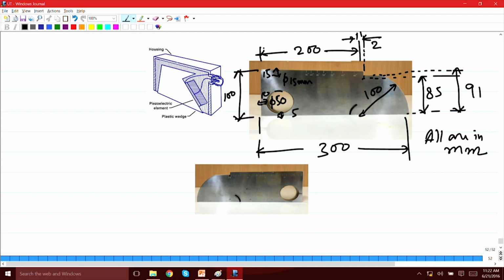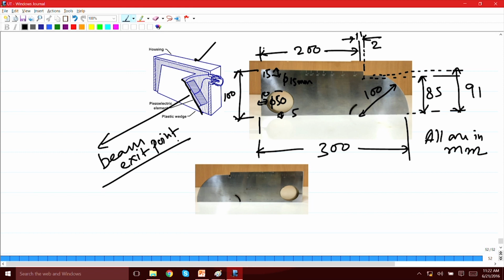This is an angle probe which is shown over here. You have seen it before also, and you have seen this plastic wedge cut over here to provide the particular angle that you need. The first thing you need to know for this kind of angle probe is where exactly the beam is exiting from this surface. Which exactly is the beam exit point? Because the angle has to be calculated with respect to that particular point.